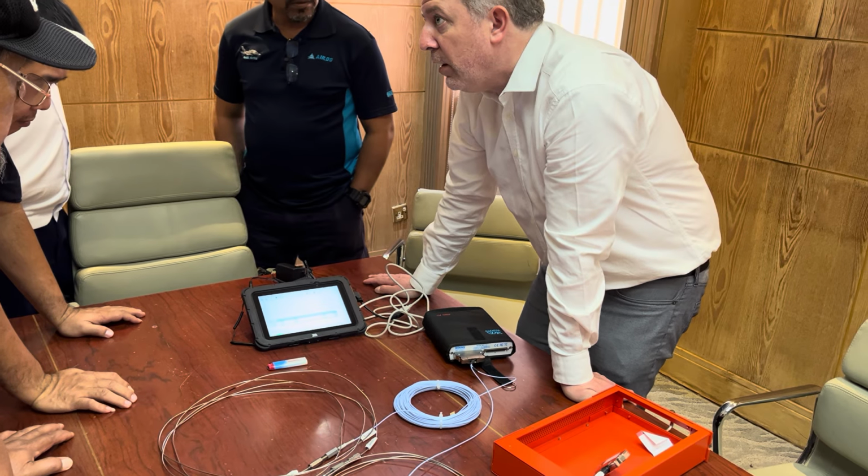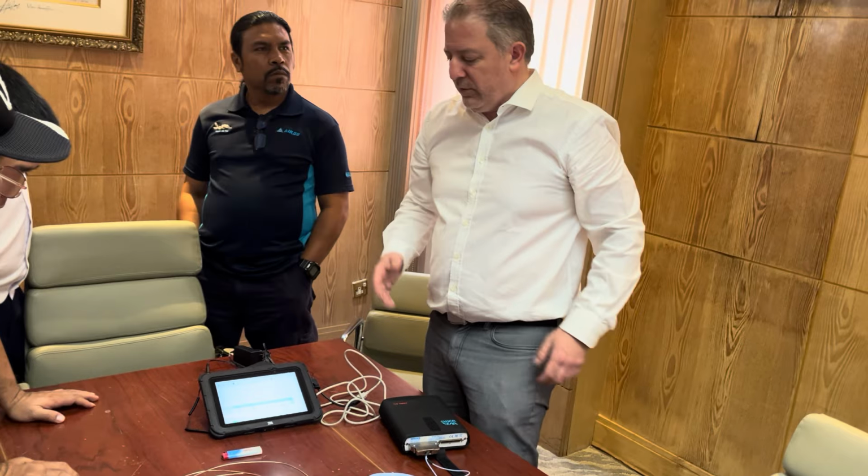So usually, overheat could be a leak, but most of the time it's not a leak, it's just an installation issue, because you have a sensing element touching the other part, and then it's going to raise an alarm even though there's no leak. Also, this kind of issue.